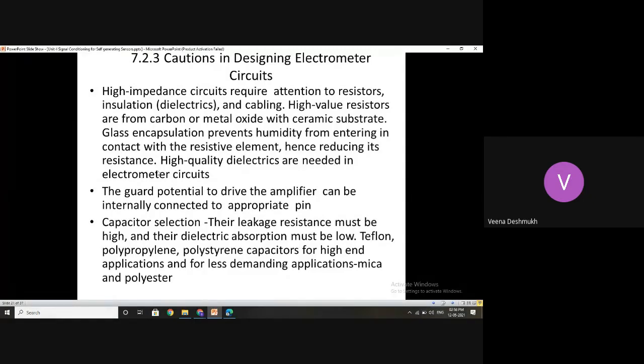So naturally the resistance will change. You calibrated it for some value, but due to the metal oxide or carbon reacting with H2O, the resistance changes because the chemical composition changes. As a result, your calibrations go wrong, the impedances go wrong, and the electrometer functioning gets affected. So they have to be of high quality, mounted on ceramic substrate, and encapsulated in glass envelopes.